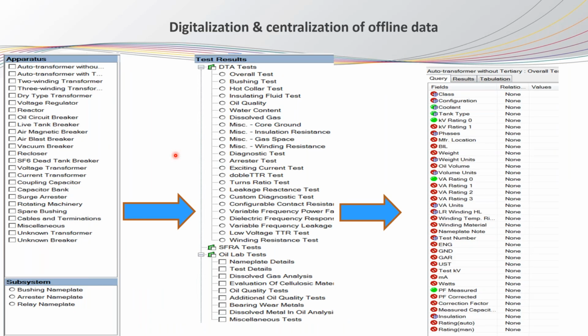In the end, you can extract the offline testing of any family of transformers in your fleet. You can simply select here what transformers you want to extract. So I can select 2 winding transformer, and here what test results you want to display or extract. I can select, for example, overall test, which is a power factor, excitation current, turns ratio. Okay, and here what parameters from this test you want to display. So I want to display, for example, the kilovolt ampere of the transformers, the type of the cooling of the 2 winding transformer, and also the power factor measured value. And you can extract these values, you can do your analysis, you can do a comparison for the transformers from the same manufacturer and see if there are any kind of deterioration symptoms. So this was for the offline data.